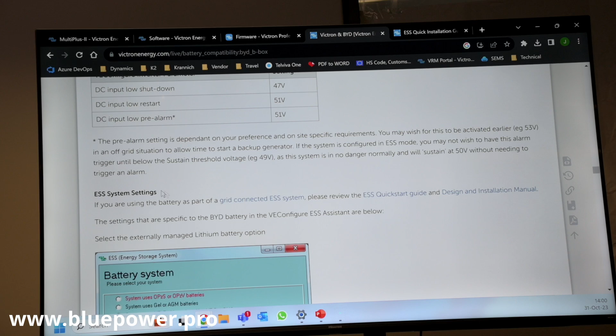So here we see battery system. They indicate that we must select the one which is LiFePO4 with other type BMS. This can be a BMS connected via CAN bus, or a BMS system in which the batteries are protected by external equipment. So 100% of the time, if you install a lithium battery, you're going to select this battery type.